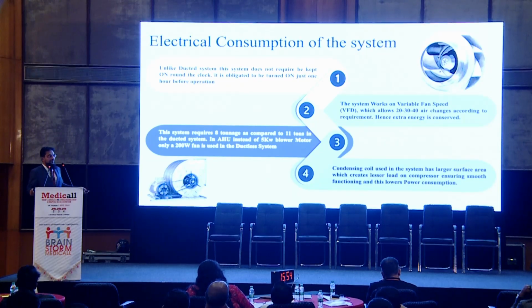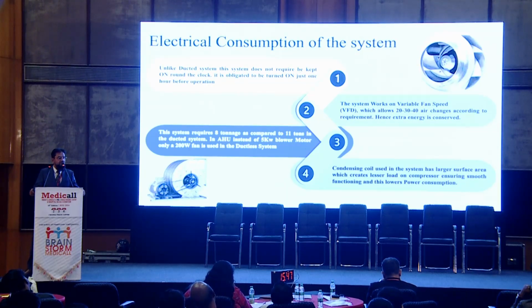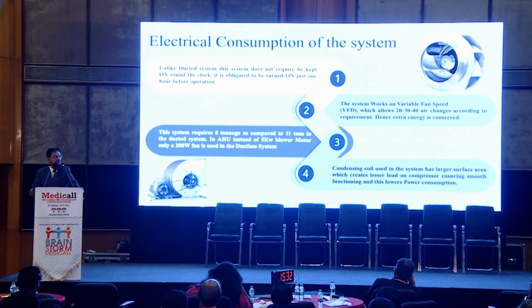Then the tonnage requirement will also be less. Normally, ducted systems require 11 tons in a 20 by 20 operation theater. This can be achieved with 8 tons also, considering that the outside ambient temperature is 50 degrees. In some areas this year, temperature goes up to 52 also, in the Delhi and Lucknow area. Even at that time, you will not find cooling problems.